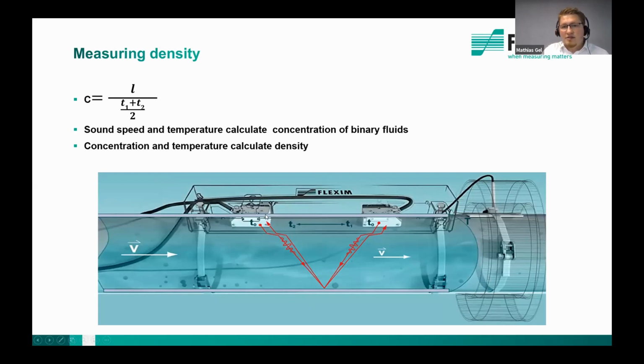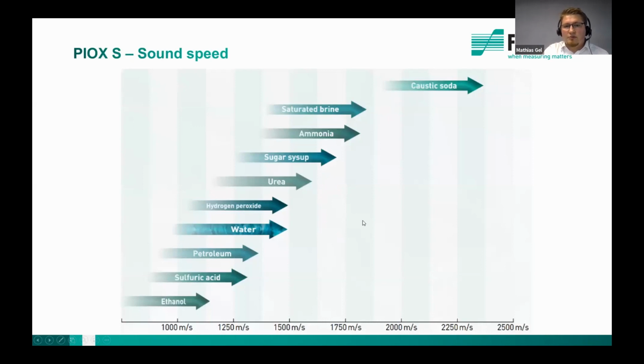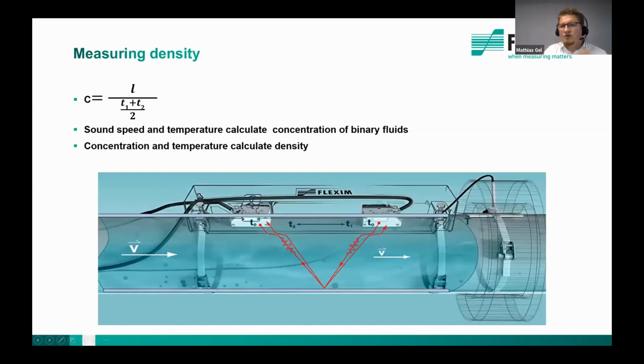We have here 2 sensors installed on the pipe. They send a signal back and forth, just like my colleague explained. And what we do is we measure this time already for the flow measurement. And then if we divide this time by 2, we have the average traveling time. And we know the geometry of the pipe. We know the distance between the sensors, so we can calculate in the triangle the distance traveled by the sound signal. So we have a distance, we can divide it by a time, we have a sound speed.